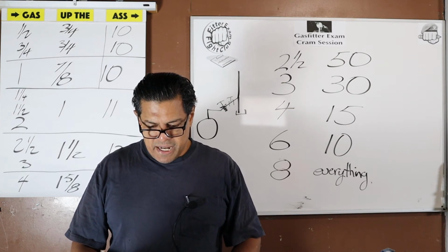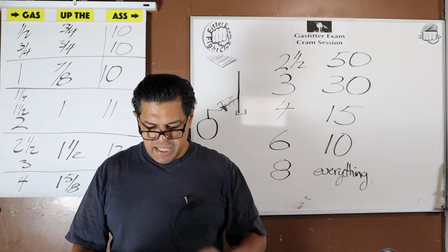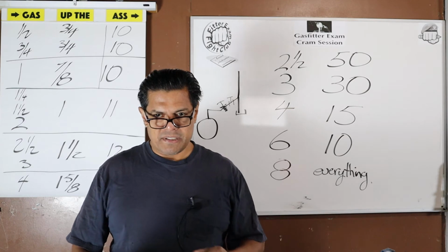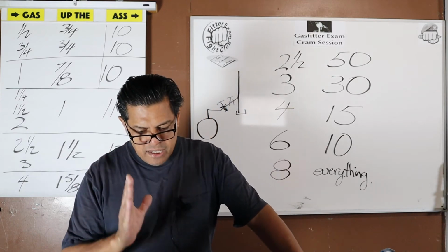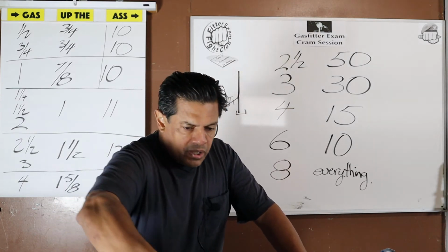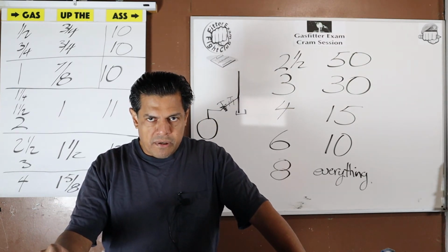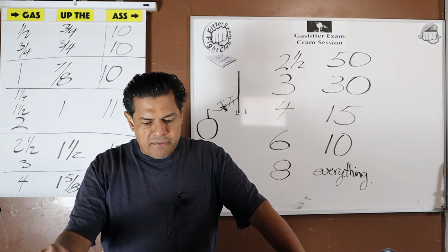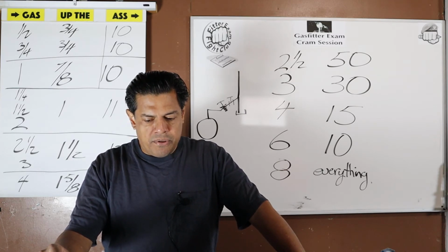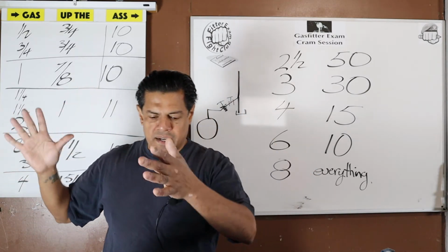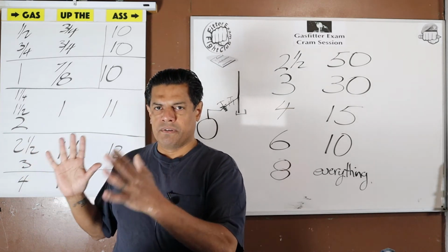Question 11. Piping systems may be purged indoors with fuel gas if the design operating pressure is 2 psi or less. Here's another one. Not that I'm holding information back from you, okay? You're going to get to see everything, but in order to pick up huge bodies of information, you've got to start with the most important, and you've got to build a foundation.